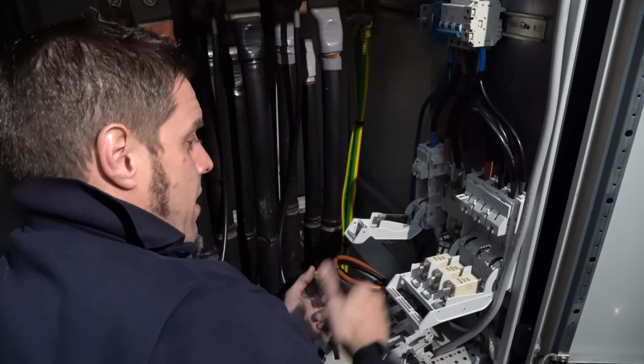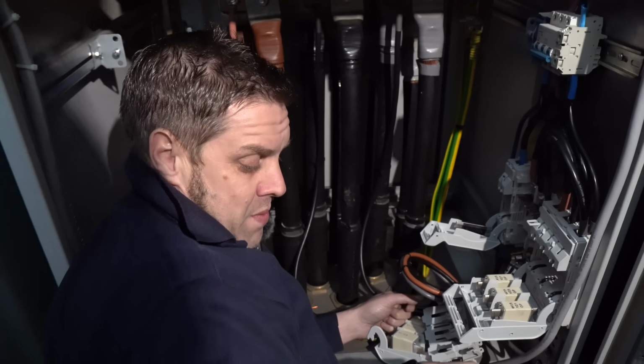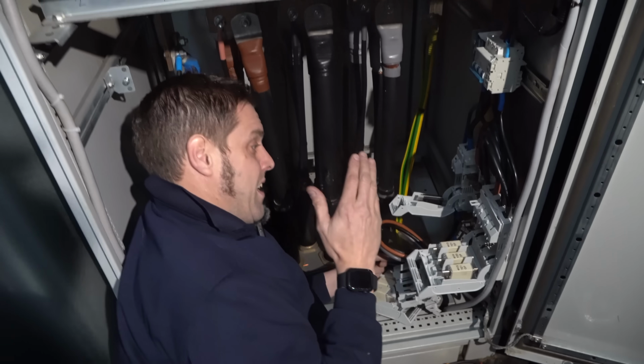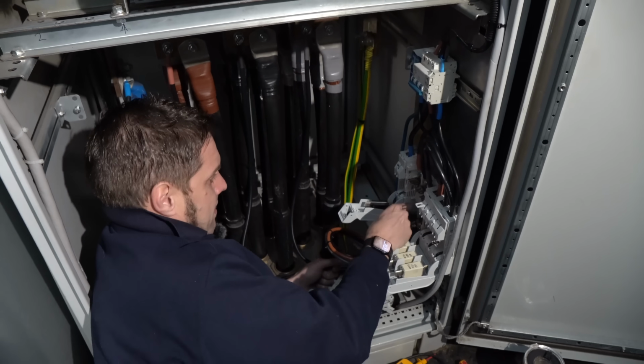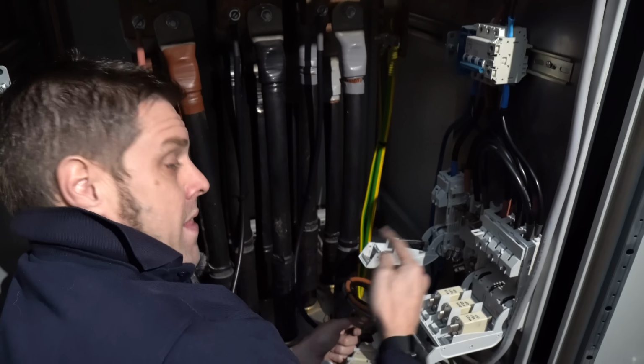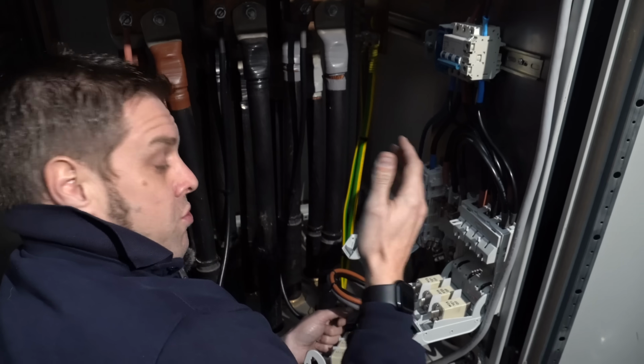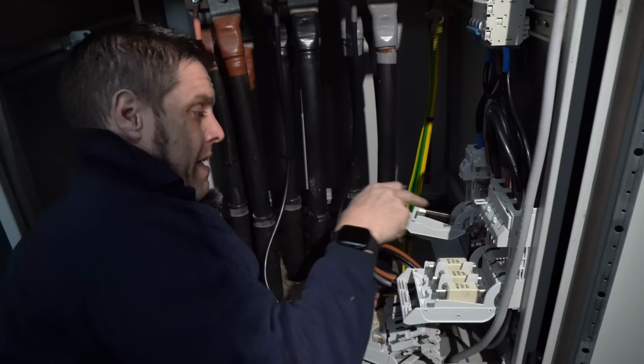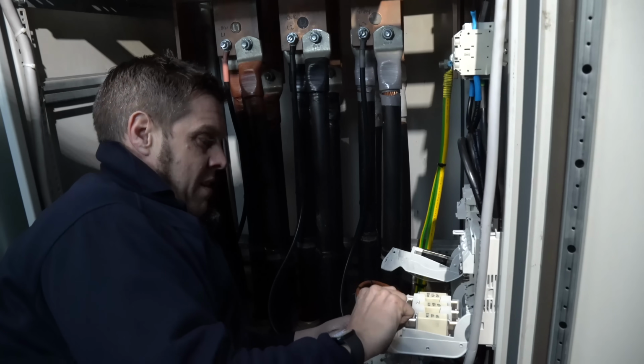That's not right. So unfortunately, even though we've stopped here till 10 to 9, if we energise this cable, this is the first carrier after these. The potential fault current on that, if it touched that earthed back plate... there's 2,500 amps on it anyway, and the transformer's just outside, so the prospective short circuit current is massive. It would be worse than the job we came here to fix, so it's just not worth it.